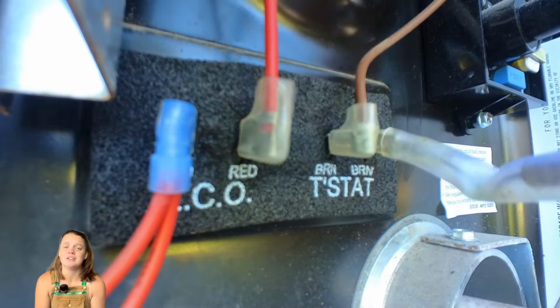So again, we're going to pull out a little bit on the terminal, on the side that is coming in from the circuit board. Again, when we go to pull out on that terminal, use a finger to support that little ECO. Pull out on that terminal. There's a spring behind it too. Don't allow that spring to pull back and smack against the side of the tank. You will be sad. Don't be sad like me. Use your finger.